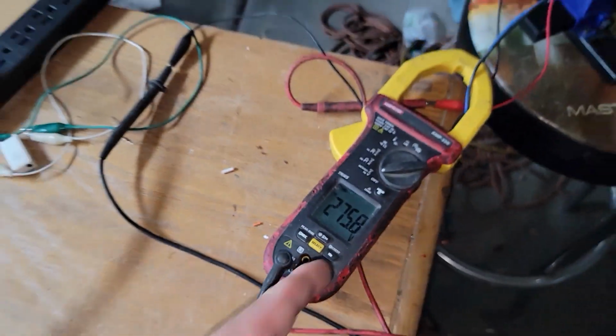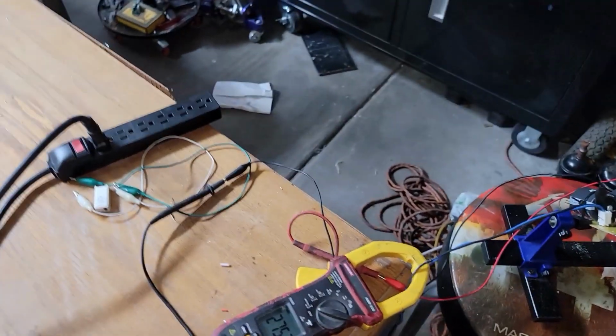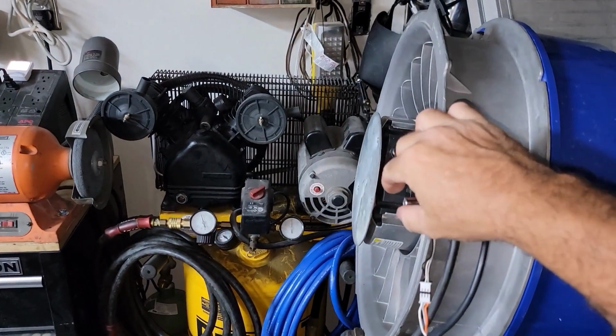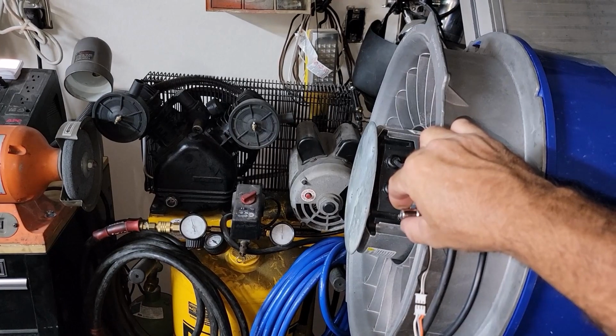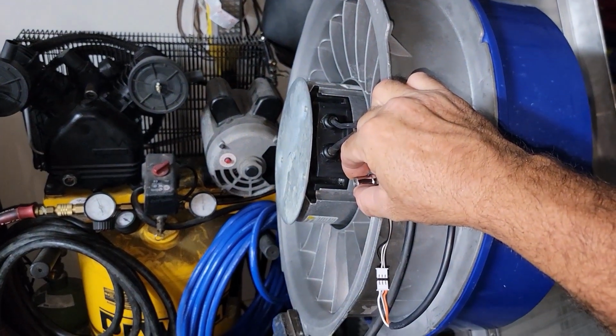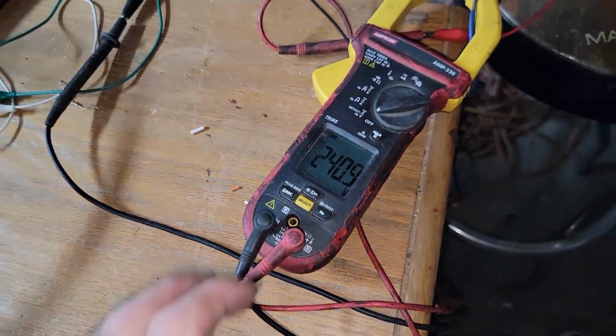There's 5 amps. I'm going to switch over to voltage because I know I can get down to about 240 before it really trips. It gets down to like 230 something, 220 before it will stop on low voltage. So we're just going to push it here. There we go, it's probably getting there.